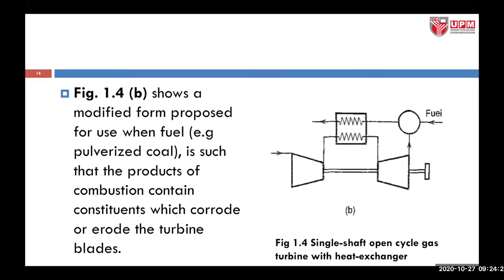Figure 1.4B shows another modified form proposed for use when fuel such as pulverized coal is being used. Instead of having the combustion chamber connected directly to the heat exchanger, the air is heated by the heat exchanger before being supplied to the turbine — the air is pre-prepared, its energy and temperature increased — and then it is supplied to the combustion chamber, so the incoming air for the combustion chamber is at a much higher temperature compared to the earlier arrangement.